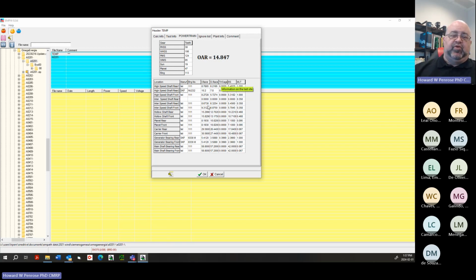That becomes important when we talk about lubrication related issues, especially on main bearings. For instance, I can tell you if you're having a lubrication problem, like somebody didn't properly flush a bearing on the main. Part of the project we're doing now, looking at ground systems, we're also checking if we're seeing fluting damage on main bearings. All of that will show up from your generator data. I love that part - how is that possible? Because we're seeing the whole system all at once.